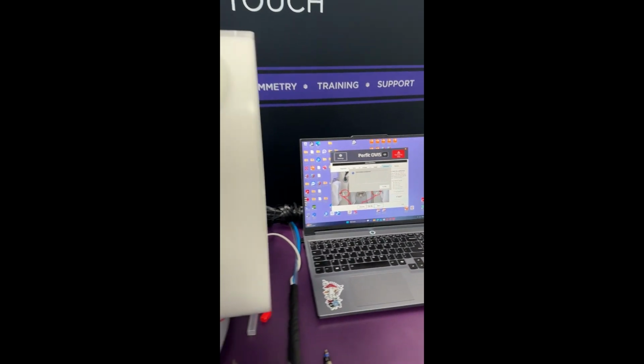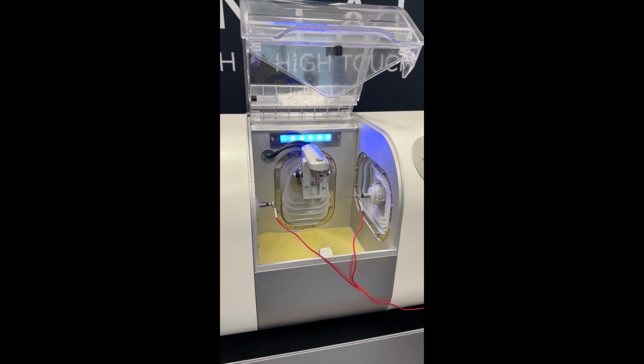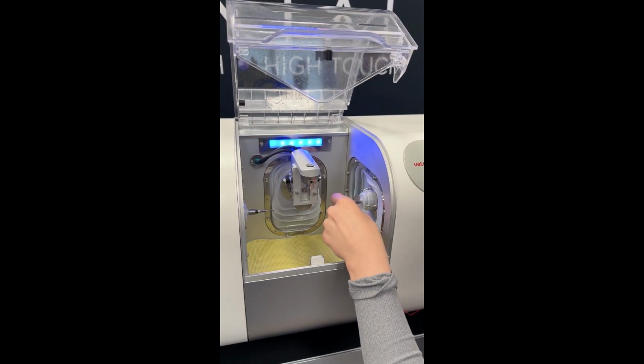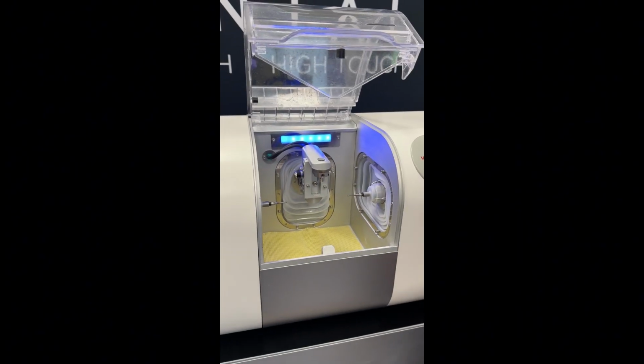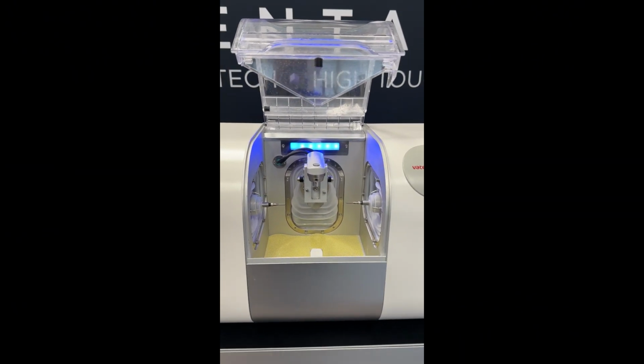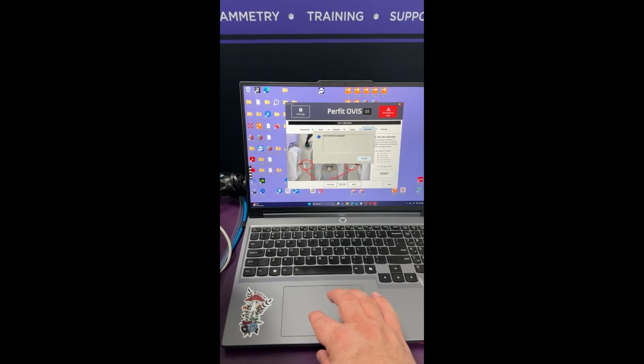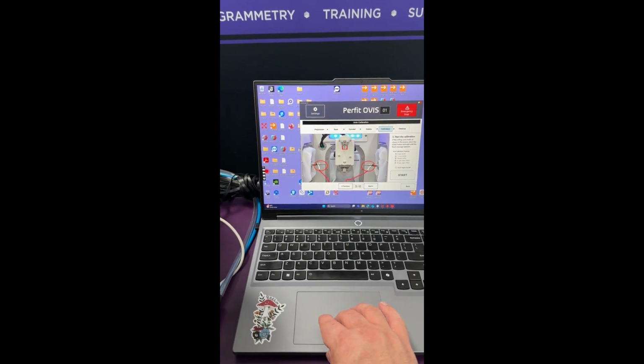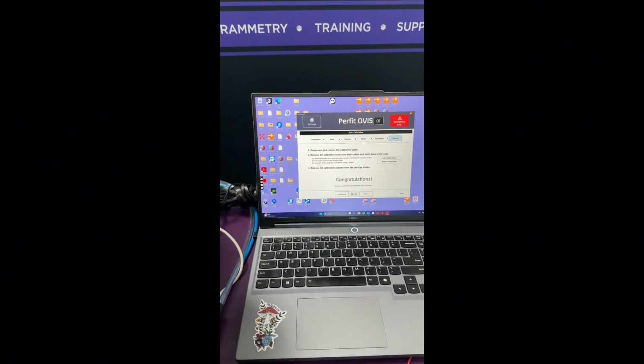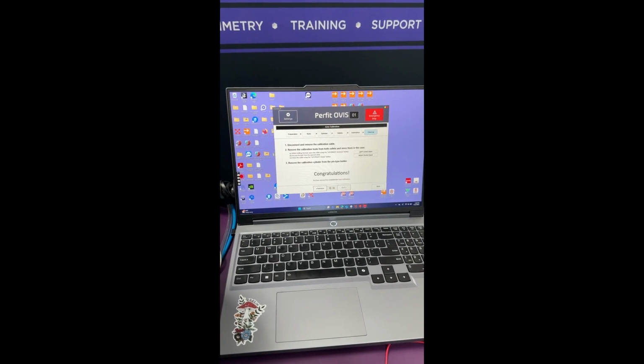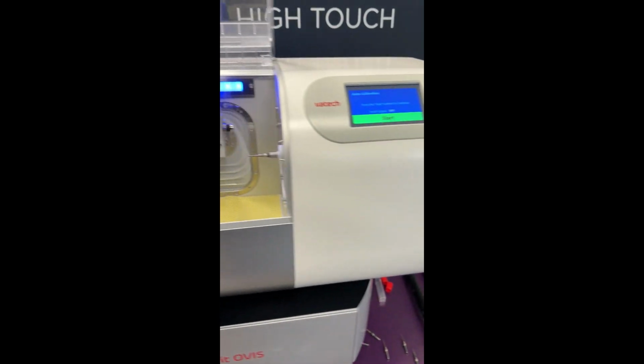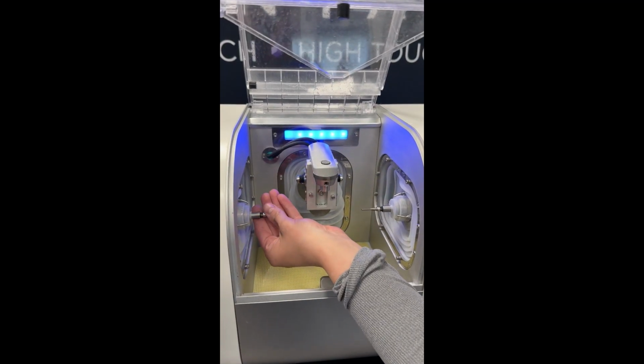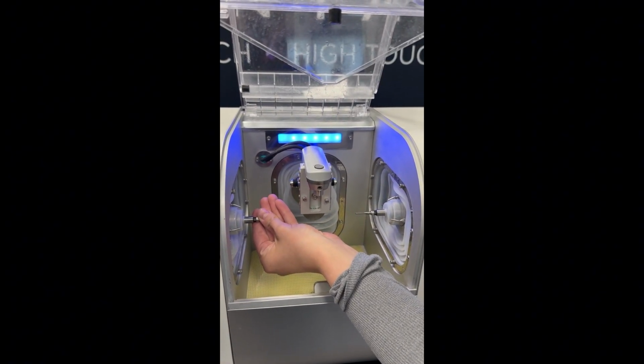Okay, at this point the calibration is completed, so we just need to take the calibration cable off the spindle, unplug it from the back of the machine. And we can close this, and the next step, we're finished, and then we just remove the dummy tools from the collets again, just like we did before. Hold them and then release in the software.